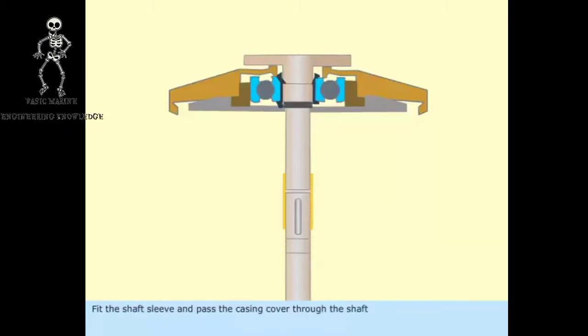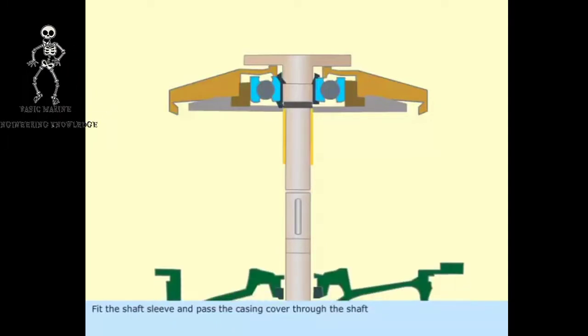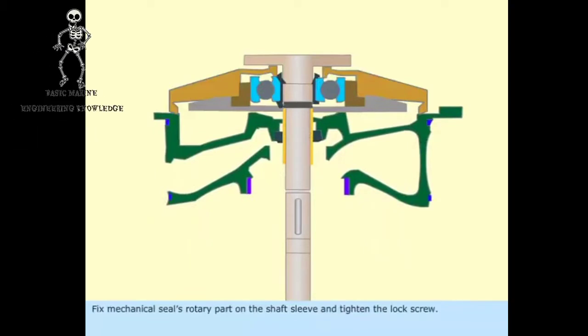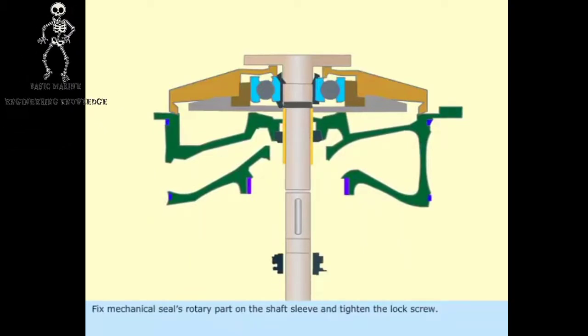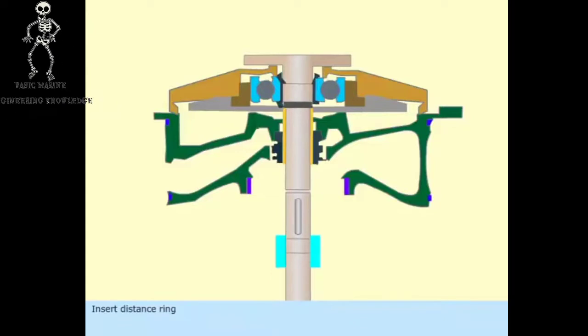Fit the shaft sleeve and pass the casing cover through the shaft. Fix mechanical seal's rotary part on the shaft sleeve and tighten the lock screw. Insert distance ring.